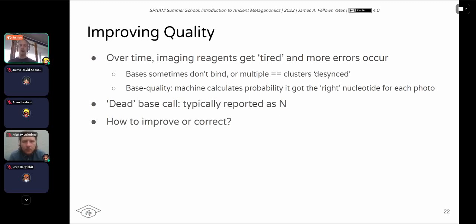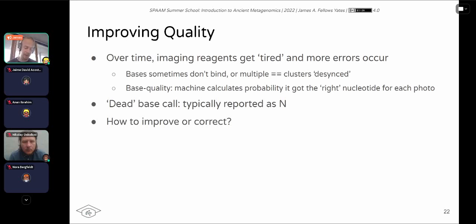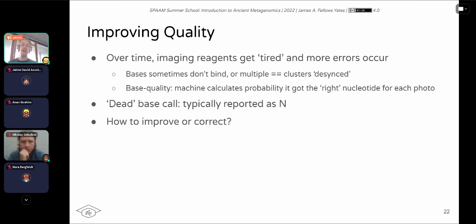Something to consider is that biology is not perfect. Over time the imaging reagents get tired, polymerases start making mistakes or don't bind properly, and more errors occur. Sometimes nucleotides won't bind, meaning you'll skip a base, or multiple nucleotides get added at once, and within your cluster the DNA molecules emitting light get desynced so the colour becomes blurry and less clear. The machine calculates a base quality score — the probability that it captured the right colour — and if it has no idea it will call a dead base, reported as an N.